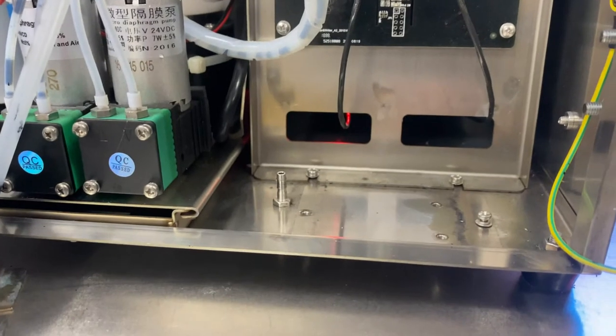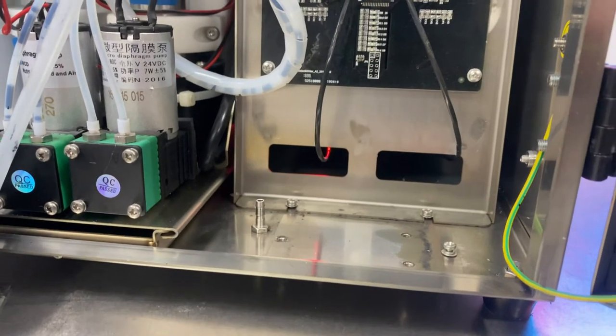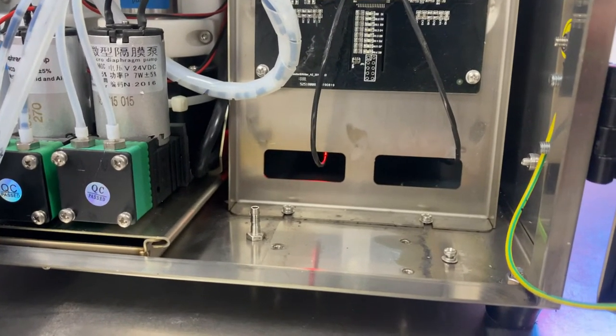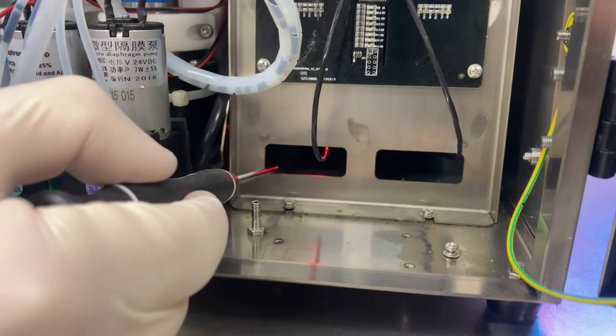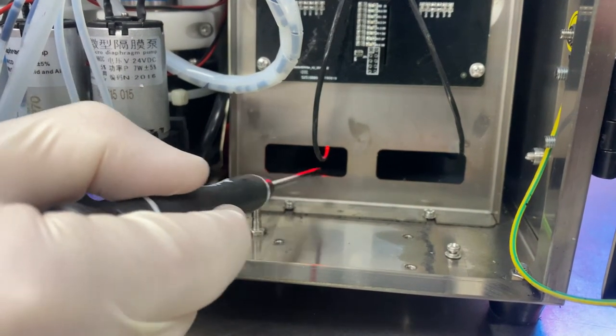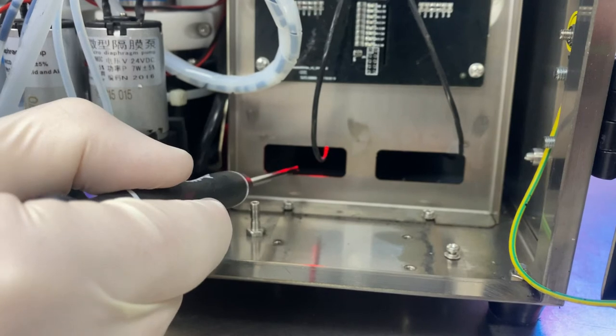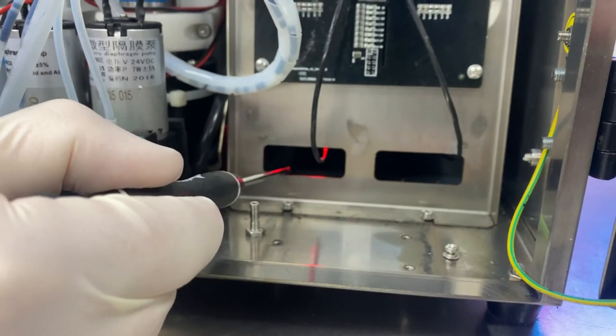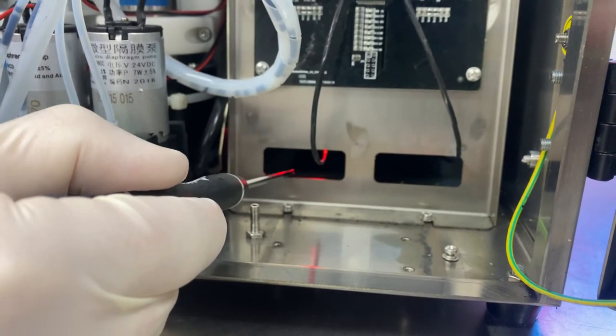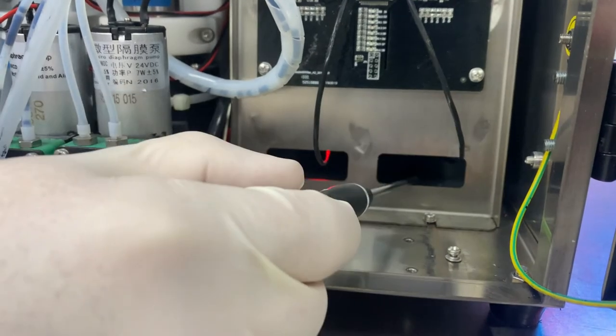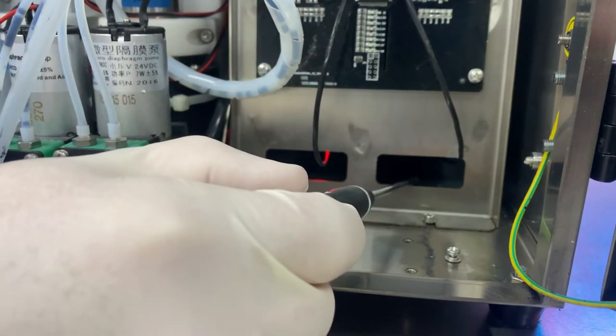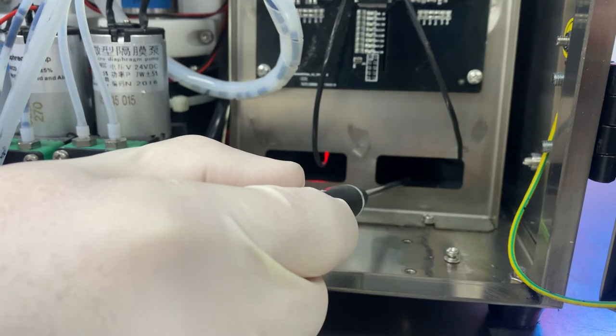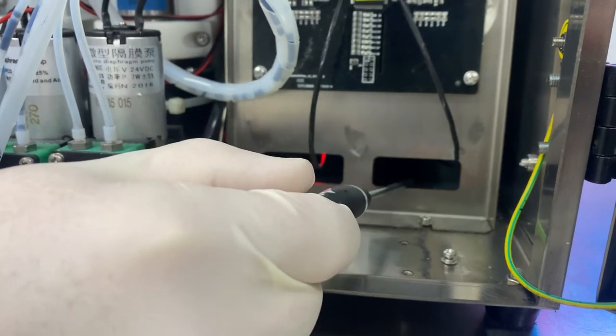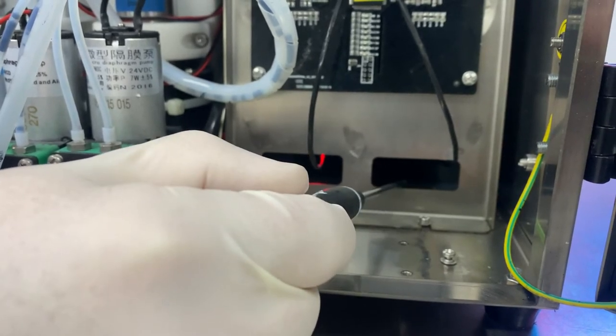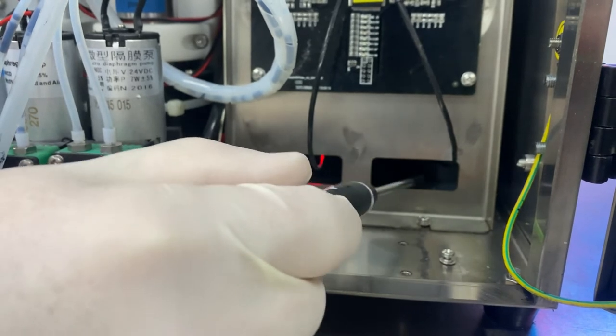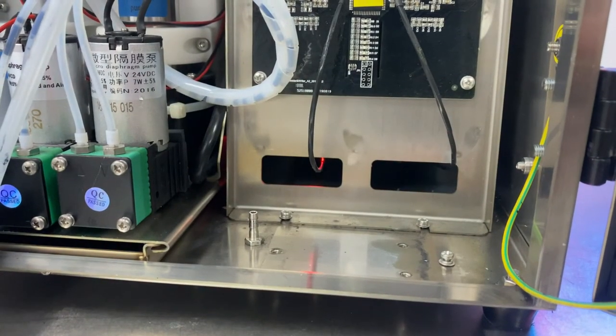Now we can see the underside or back of these sensors. One thing you'll notice right away is we've got a red LED on the makeup side, so we do have a makeup cartridge inserted. The red light indicates it's detecting fluid. The ink cartridge sensor functions the same way, so if we have a full cartridge inserted, or a cartridge with fluid inserted, we should have a red light here. I'm going to put in a cartridge really quick so you can see that light turn on.